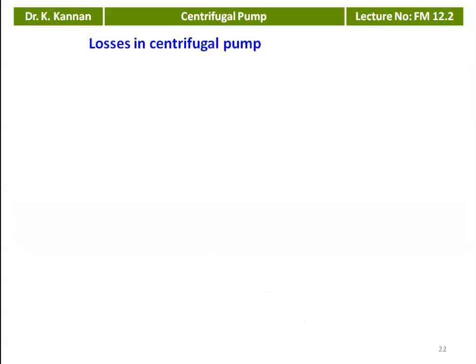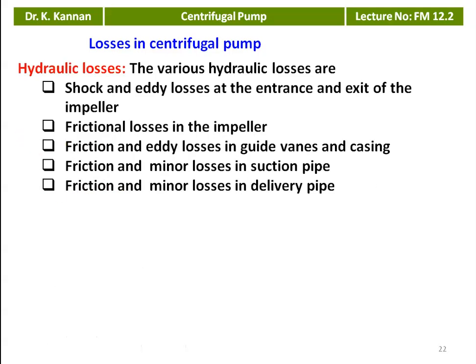We calculated the manometric head equation in the previous lecture. There are some losses in the centrifugal pump. The first loss is hydraulic losses. The various hydraulic losses include shock and eddy losses at the entrance and exit of the impeller. Eddy losses are due to turbulent or circulatory flow of the fluid particle, and there will be shock as fluid suddenly enters the impeller.